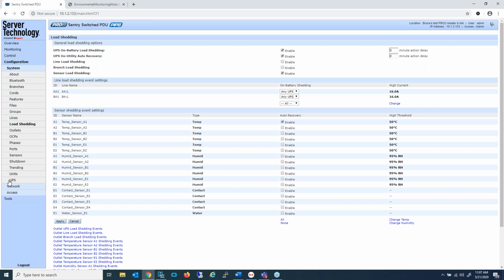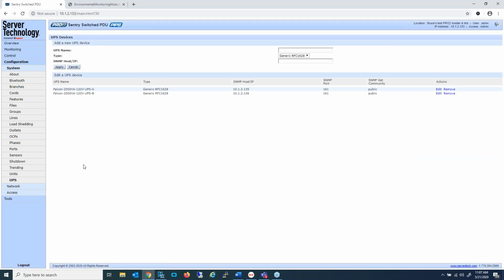So the first thing that you would look at for using the on battery load shedding would be the UPS configuration. So configuration, system, UPS. This is where you define the UPS systems that exist upstream of the PDUs. The PDU system allows you to define up to 8 different UPS systems. Presently, there's no purpose to have more than 4. One master PDU can support being linked to up to 3 link PDUs, in which case you have 4 separate PDUs, up to 4 separate circuits. So today, there could be use for you to define up to 4 UPS systems.